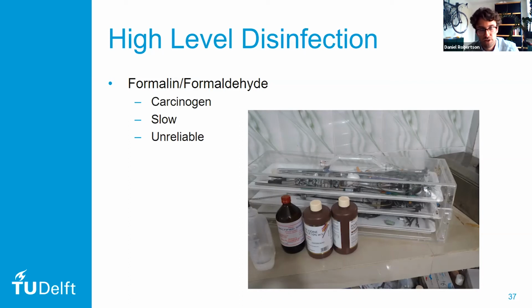Now, what we also saw is that sometimes these boxes were used in between patients, so that the instruments after one patient were cleaned, placed in the box, and then 20 minutes afterwards, they were retrieved out of this box, and the box would be opened multiple times in between. So there's not even time for the gas to properly build up in these boxes. Formaldehyde even needs many hours to sterilize the devices in the first place. So if you leave these instruments for 20 minutes in these boxes, your instruments are just not sterile for use. And one other thing about formaldehyde is that it's a potential carcinogen. So it's very risky to have these boxes in places where you continually work.